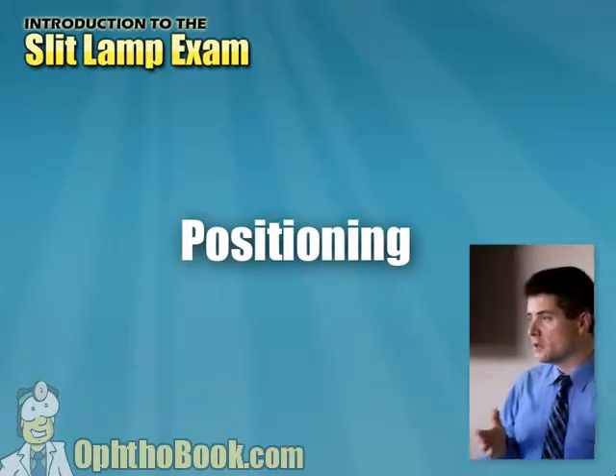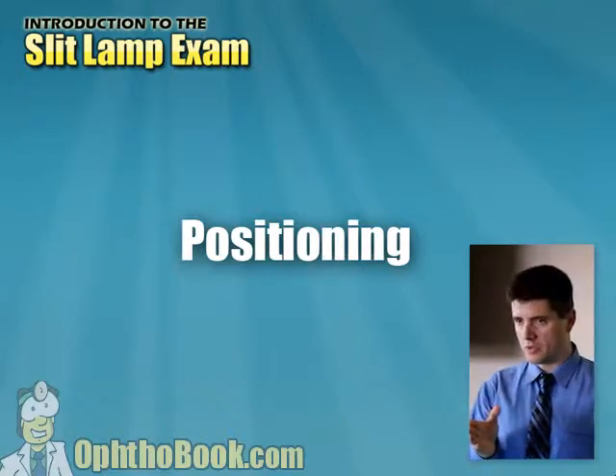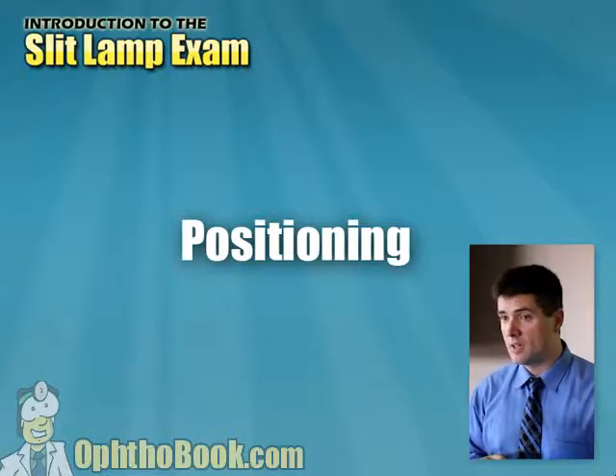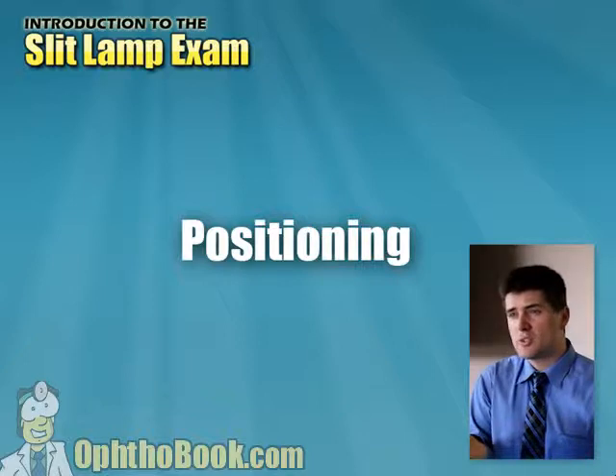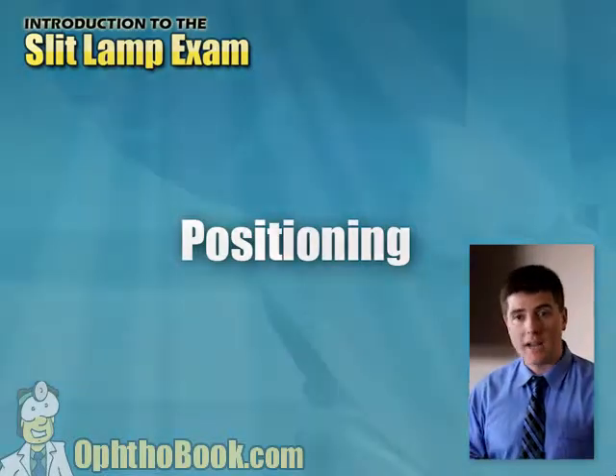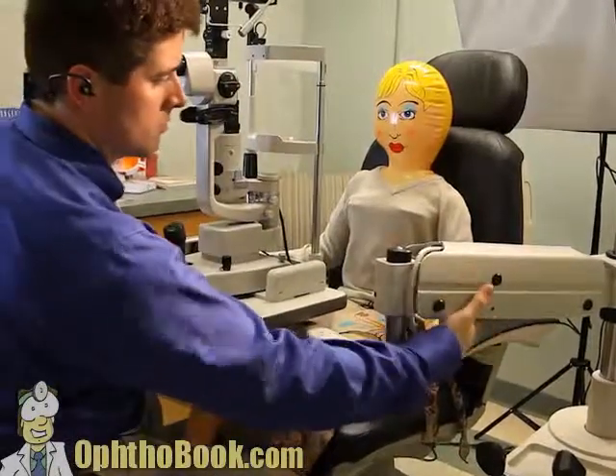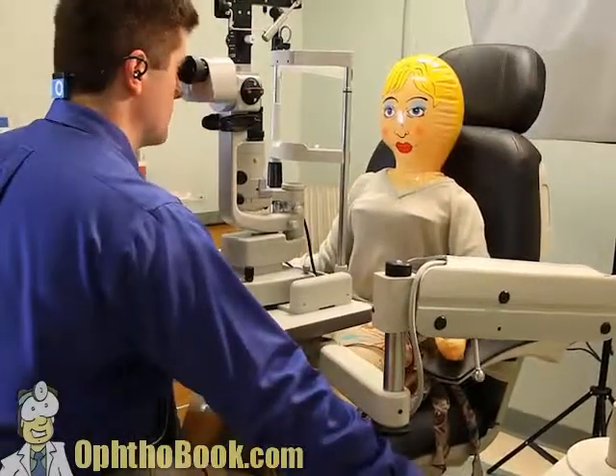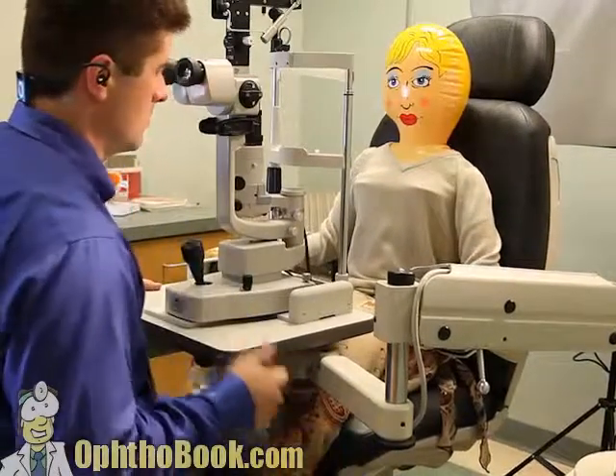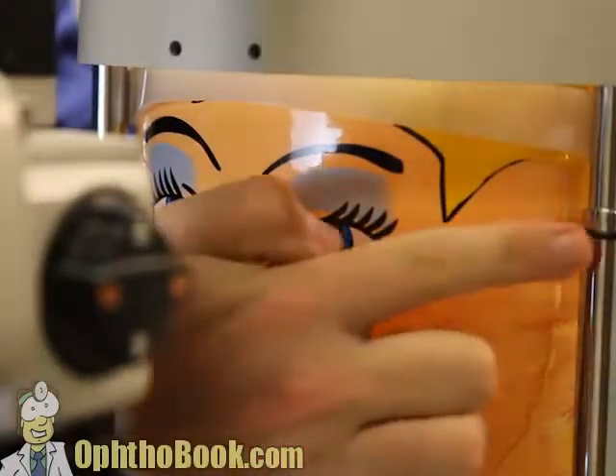Positioning — we've been trained from a customer service standpoint to always put your patient first, but when it comes to the slit lamp exam, your comfort is actually more important. A patient is examined once or twice a year; you're doing this three or four thousand times a year — talk about repetitive stress injury. So make yourself comfortable first: set your seat, set the microscope at the height you like with the locking mechanism, and only then set the patient comfortably. Get their forehead against the bar, chin on the chin rest, and line up the lateral canthus with the black mark for maximal excursion.